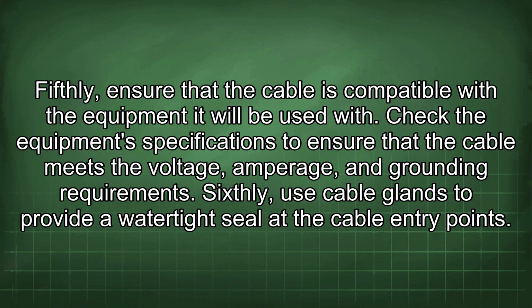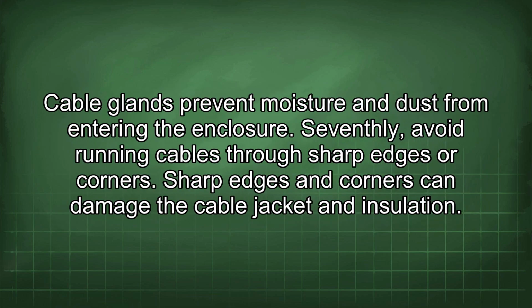Fifthly, ensure that the cable is compatible with the equipment it will be used with. Check the equipment specifications to ensure that the cable meets the voltage, amperage, and grounding requirements. Sixthly, use cable glands to provide a watertight seal at the cable entry points. Cable glands prevent moisture and dust from entering the enclosure.